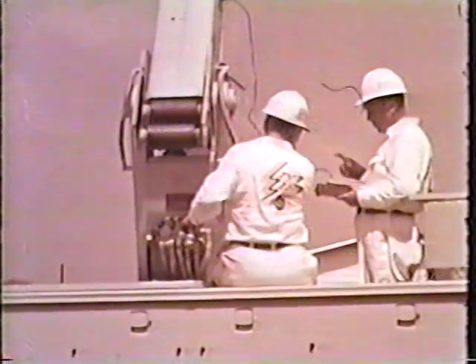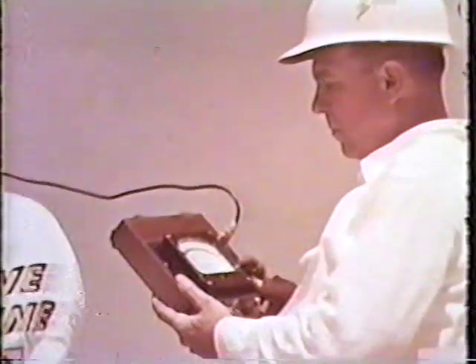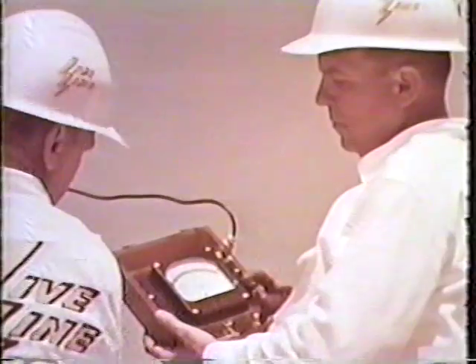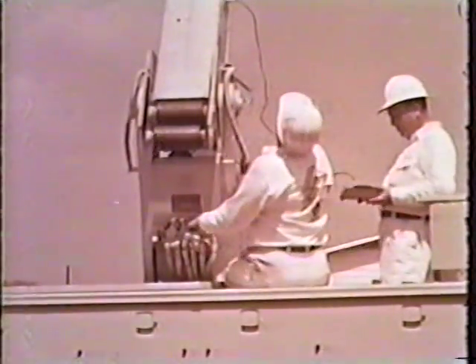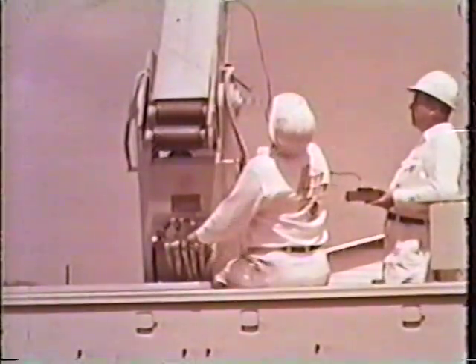With the shielding of the empty buckets in contact with the conductor, the arm current can be read on the microammeter plugged into the coaxial cable outlet. If the meter reading is normal, work may proceed. If higher than the permissible level, the fiberglass arm section should be cleaned before use.